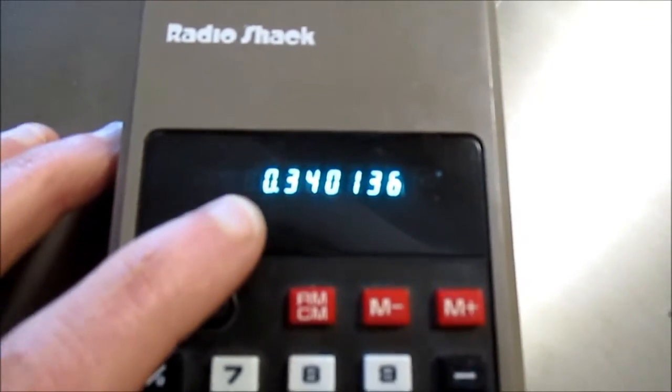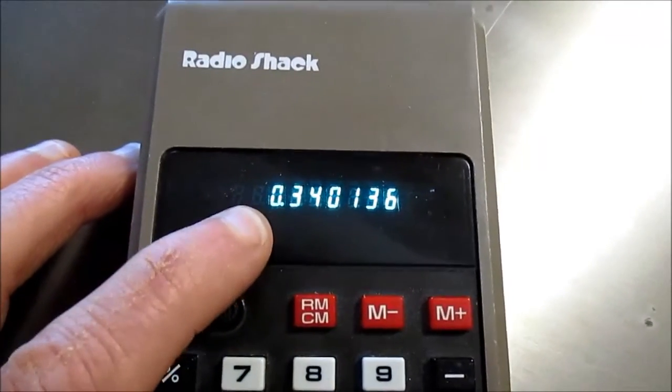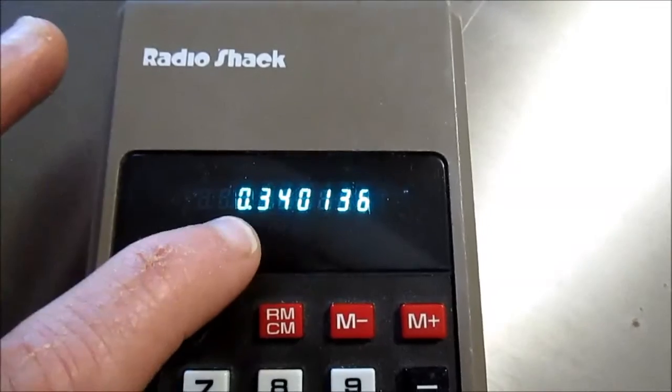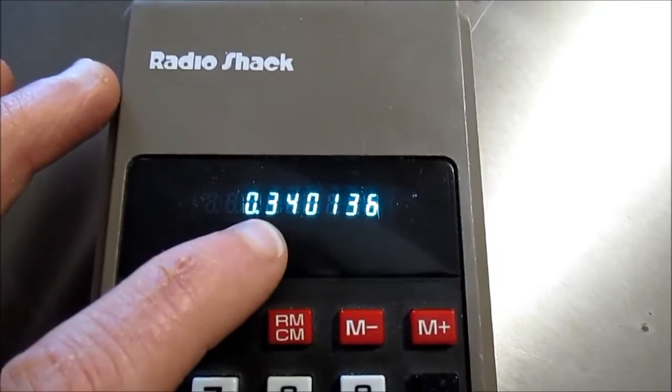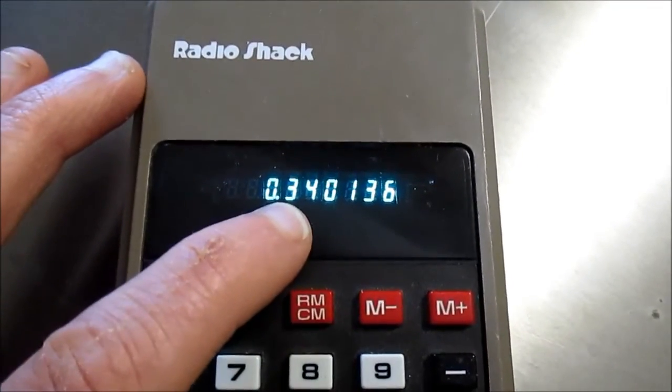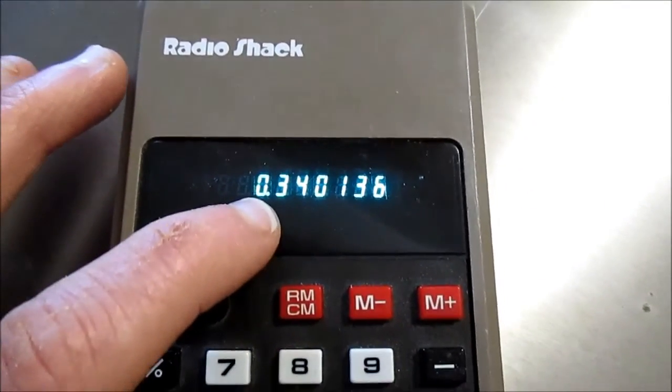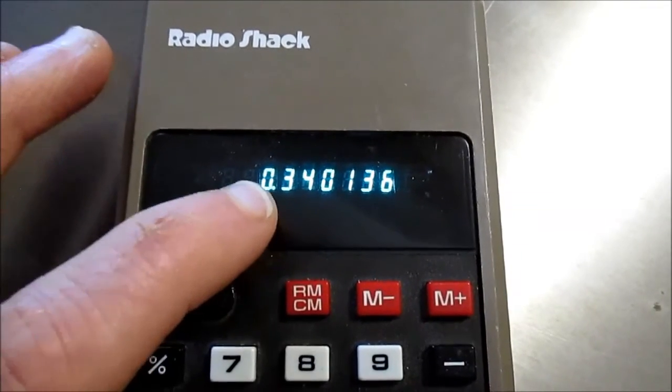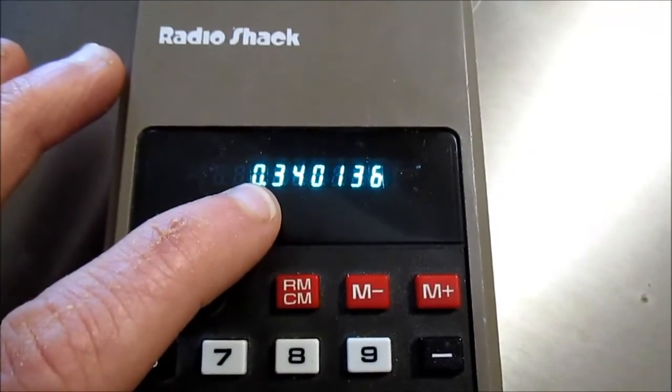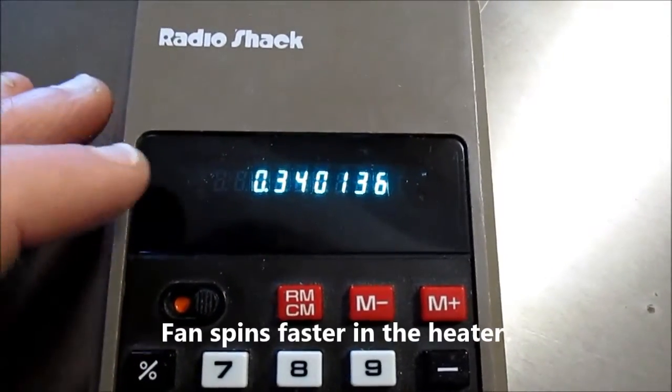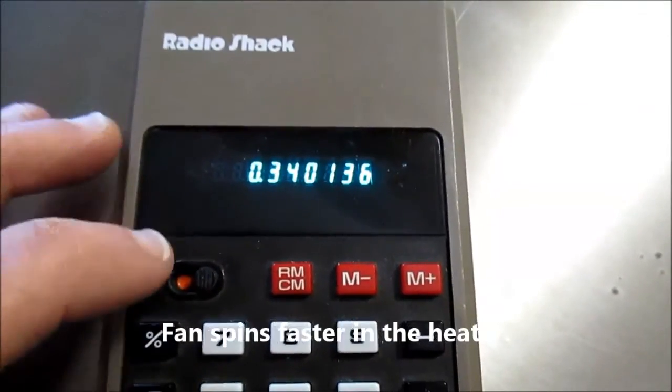And I would say it would be nice if your resistance in the wiring is not any more than about 0.5 ohms, maybe even less, 0.4. It's pretty good here. I can even tell the heater runs a little faster than it did downstairs because the voltage didn't drop as much. It was 119.7 versus...